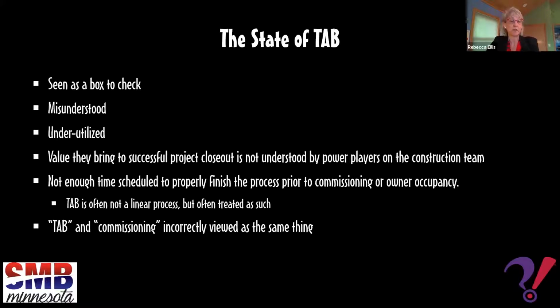So if included in a project master schedule, a construction master schedule, TAB is typically identified as a one-time activity that likely doesn't have enough days allocated to it and isn't sufficiently coordinated with completion of the systems that need to be balanced. So scheduling typically does not take into account the close coordination between TAB and controls that Miles and Mark will talk about today.